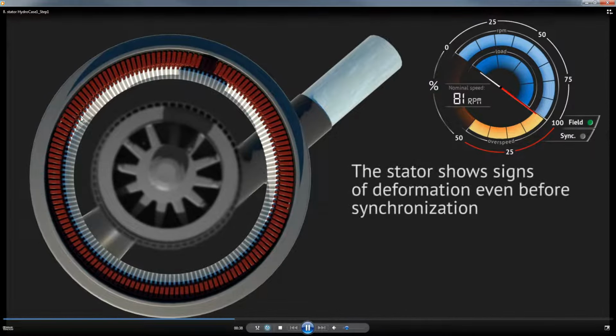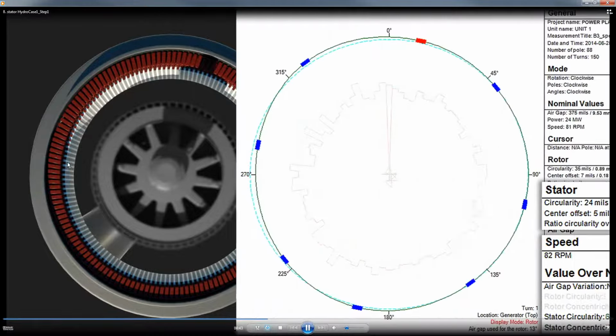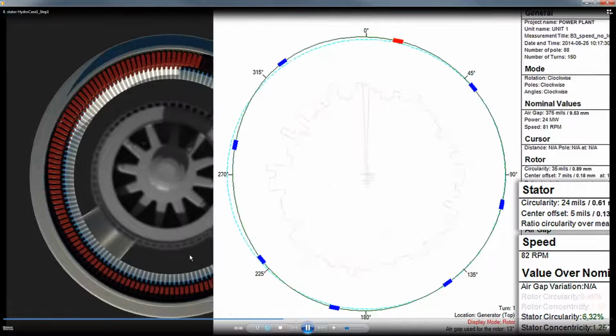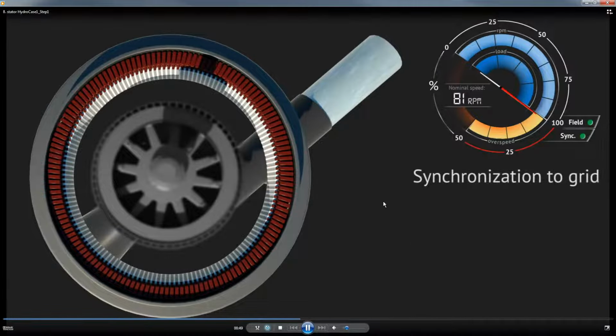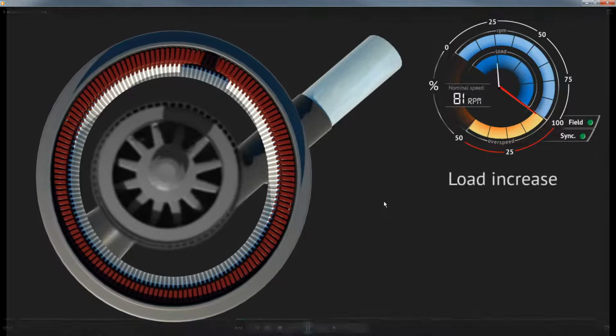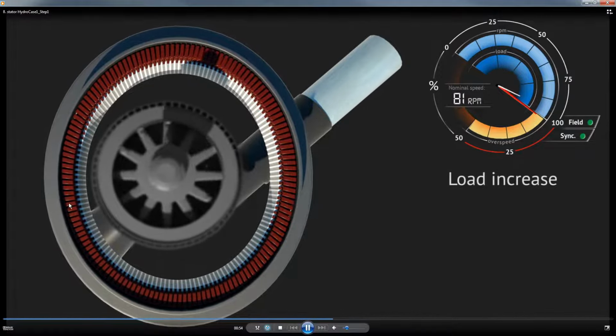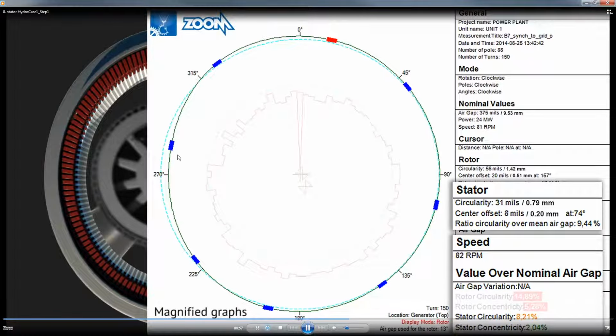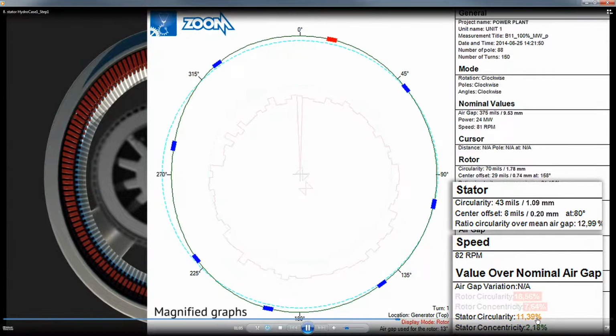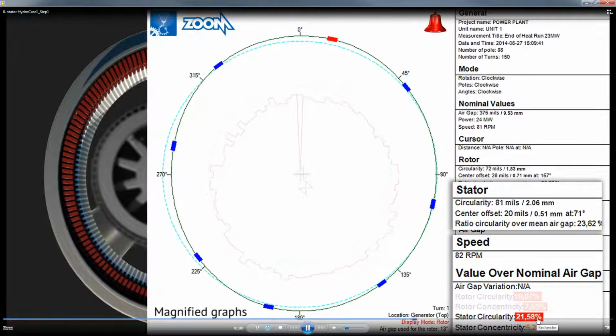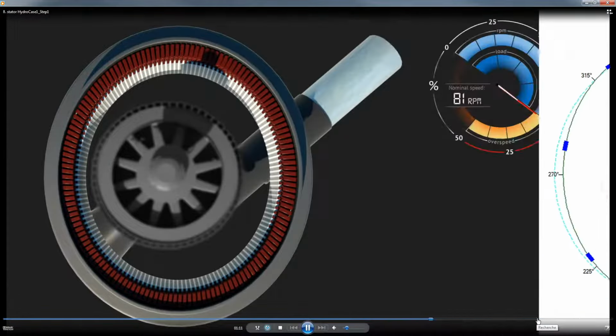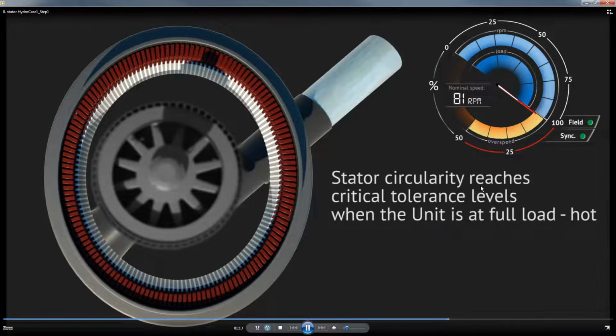Okay, so look at the encroachment of the stator even before synchronization. You can see it was already encroaching before they synchronized. And once they synchronized, the stator moved inwards at 270 degrees significantly. Okay, so you can see stator circularity initially is not so bad, but as they synchronized, stator circularity increased significantly. And I mean significantly. Okay, the stator circularity reaches critical tolerance levels when the unit's full load hot.